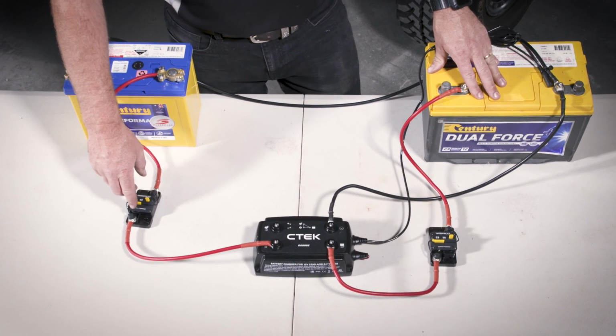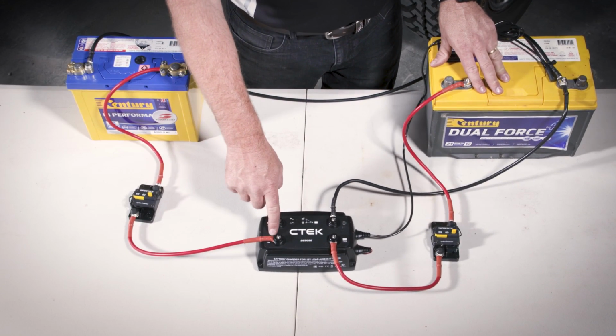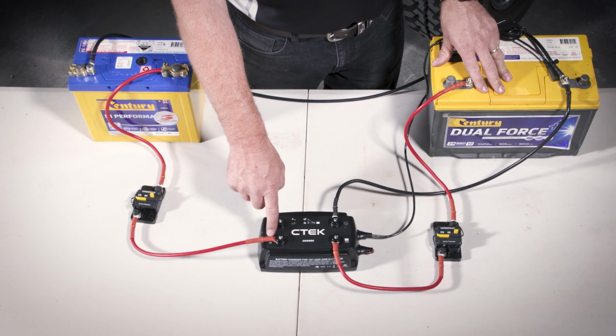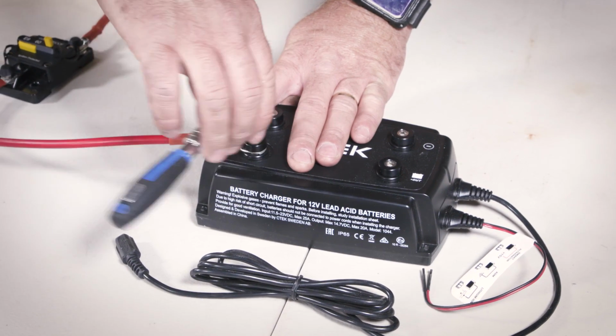We've chosen a 60 amp circuit breaker for this, then run the cable from the circuit breaker to the bottom left input terminal on the D250 SE.